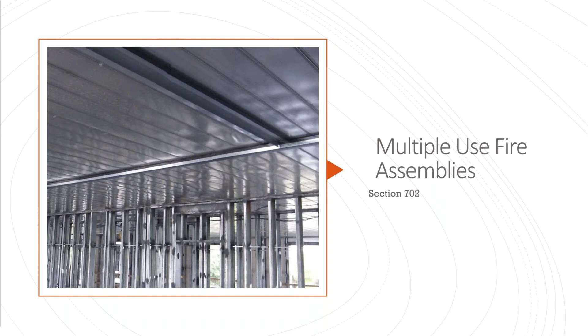And yes, we're going to talk about terminology in a minute, but the terminology shown on this slide is this way for a reason. For example, you've got corridor wall and an occupancy separation. What are those? That's a fire partition and a fire barrier. And then occupancy separation and smoke barrier, you've got the fire barrier and a smoke barrier, but that smoke barrier is going to be a fire smoke barrier. An exit enclosure to an occupancy separation, those are both fire barriers. So that's why I've named them a little different in here, just to show some common multiple use assemblies that we run into, and then corridor walls and incidental uses. In that case, you've got a fire partition and a fire barrier, but a fire barrier that's there because it's an incidental use room within that fire barrier.